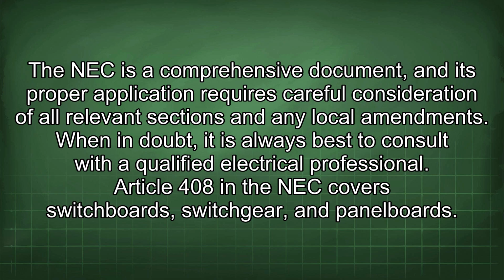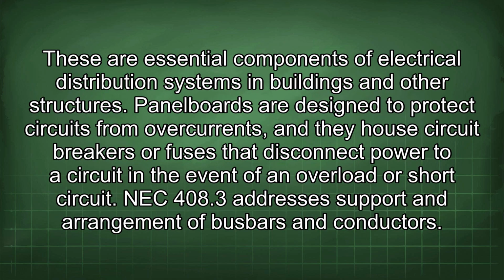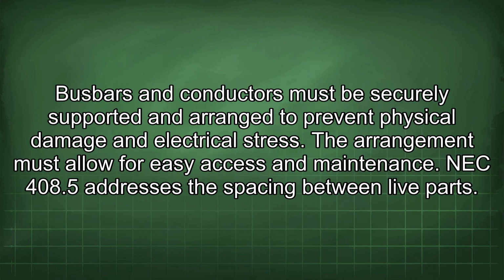Article 408 in the NEC covers switchboards, switchgear, and panel boards. These are essential components of electrical distribution systems in buildings and other structures. Panel boards are designed to protect circuits from overcurrents, and they house circuit breakers or fuses that disconnect power to a circuit in the event of an overload or short circuit. NEC 408.3 addresses support and arrangement of busbars and conductors. Busbars and conductors must be securely supported and arranged to prevent physical damage and electrical stress. The arrangement must allow for easy access and maintenance.